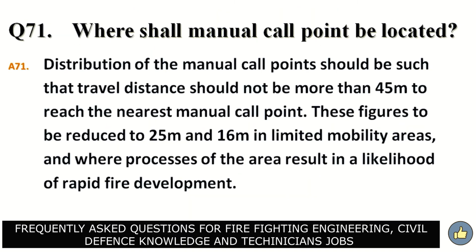Where shall manual call points be located? Answer. Distribution of the manual call points should be such that travel distance should not be more than 45 meters to reach the nearest manual call point. These figures are to be reduced to 25 meters and 16 meters in limited mobility areas and where processes of the area result in a likelihood of rapid fire development.